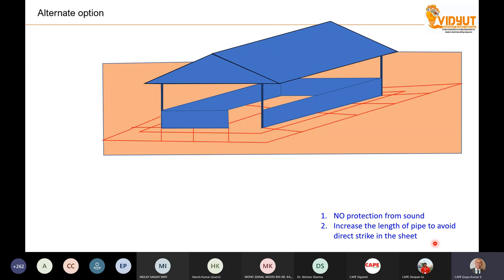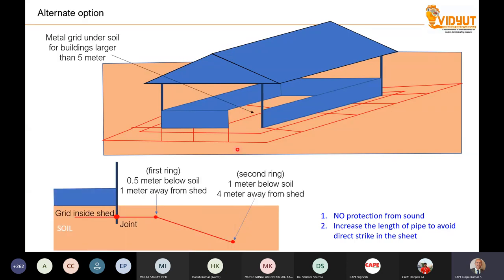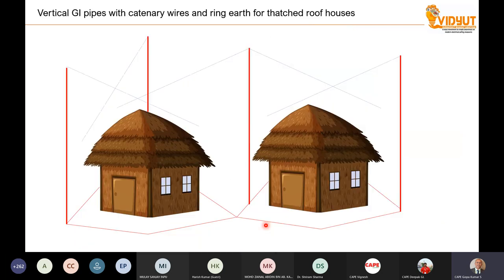But don't try to make a metal shed from tomorrow onwards. You have to properly engineer it. I'm just putting forward an idea. And another important point is you need to have ring conductors around the building, because one of the ideas is to protect people who are outside the building, or people who are coming towards the building, from step potential. So this is one idea. Probably all four sides of the building can be covered with metal sheet. As a result, you achieve the particular safety. And this is how the ring conductor shall be extended. The first ring conductor is 0.5 meter below soil, 1 meter away from the shed. And the second one can be about 1 meter below soil, but 4 meters away from the building.